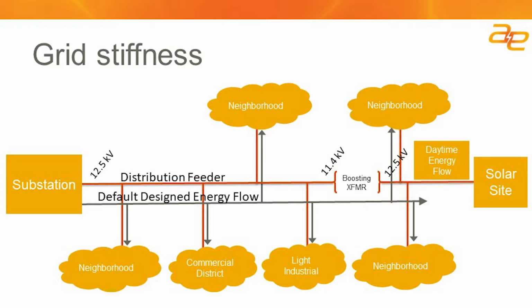So now where you've got what would be a voltage drop because of the current flowing through the distribution feeder, the utility would introduce a boosting transformer to bring the voltage back up where it had dropped sufficiently. Now when the solar site is introduced and the amount of current flowing from the substation is reduced, the voltage drop is reduced. So what might be a 1.1 kV voltage drop to 11.4 kV where the boosting transformer is, it would increase the voltage by 10%, bringing it back up to 12.5. Now the voltage at the substation side of that boosting transformer might be 12 or 12.1 kV because the current has dropped enough. And now when you're boosting that, it might be causing an overvoltage condition for the neighborhoods on the solar site side of that boosting transformer.